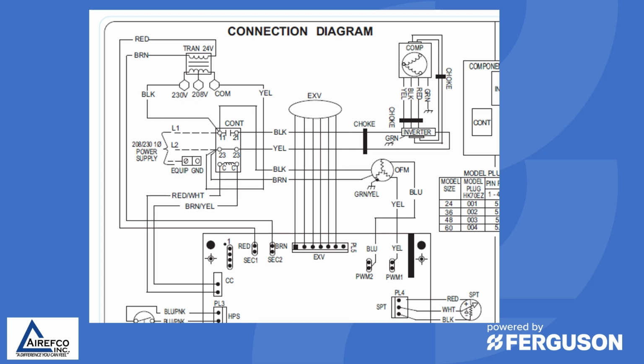So as we stated, on a lot of outdoor units, you're going to have a 24 volt transformer that is tied into the circuit board on the outdoor unit. And with the thermostat hookups, you will be generally directed not to hook up 24 volts to the outdoor unit from the indoor, because the outdoor unit has a transformer of its own.